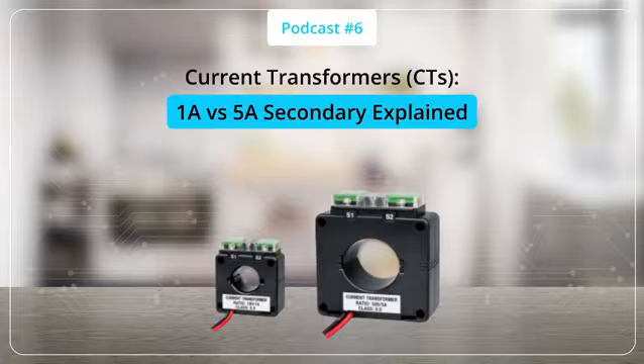A 5A CT is generally more robust and is widely used in traditional industrial systems and relay-based setups. On the other hand, a 1A CT is more efficient and provides better accuracy, especially in digital and remote monitoring systems. When we compare them more closely, a 1A CT has lower power loss and lower cable losses, which makes it more suitable for long-distance applications. However, its burden handling capability is lower.